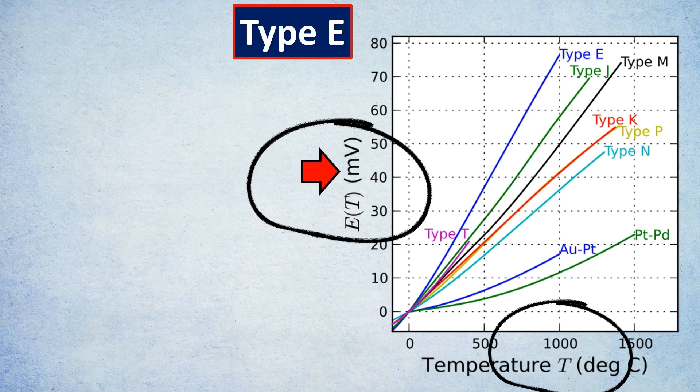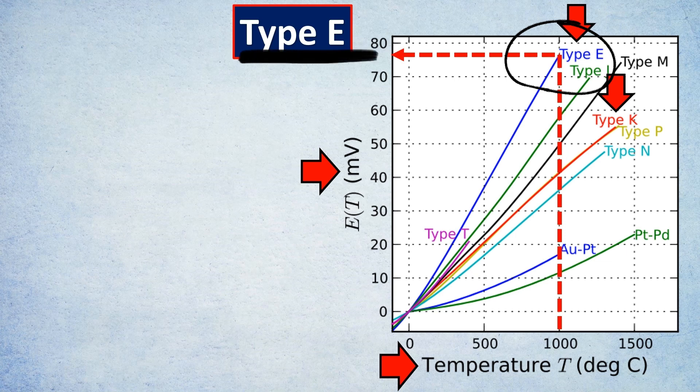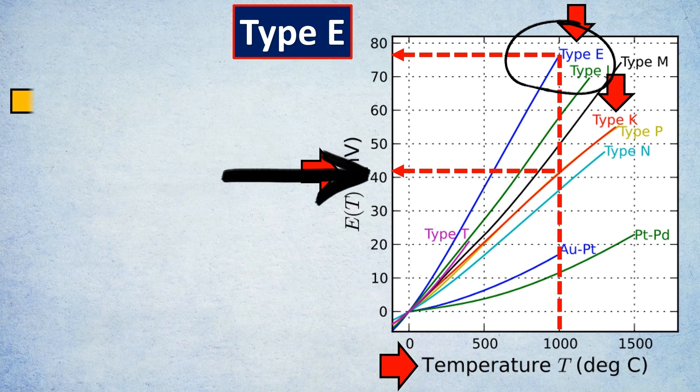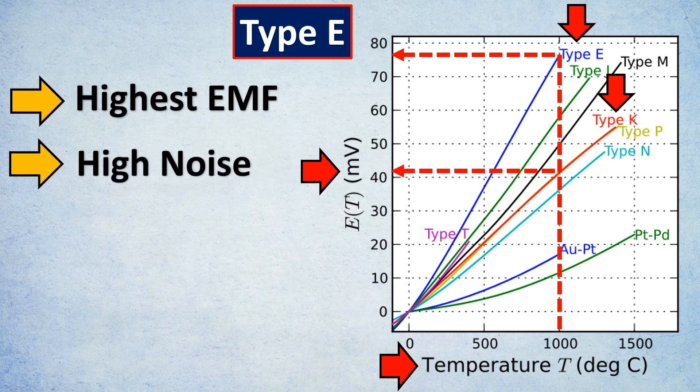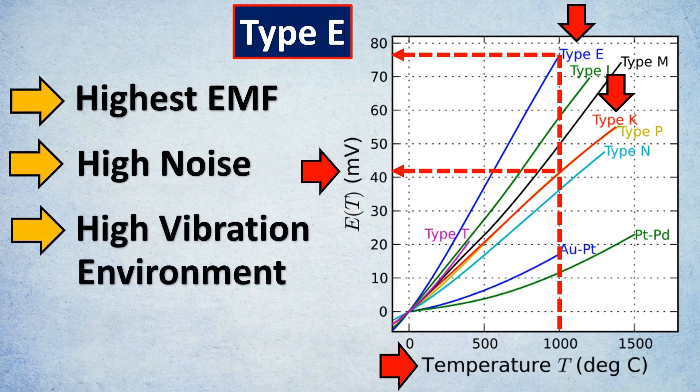Type E type thermocouple. Now if you see the EMF chart versus the temperature you would notice that for type E thermocouple the EMF generated is the highest, which is around 78 or 79 millivolt if you see. And for K type it is just 42. So in cases where you require the highest EMF that is usually in high noise requirements or where there is high vibration in the environment, E type is the most preferred type in those cases.